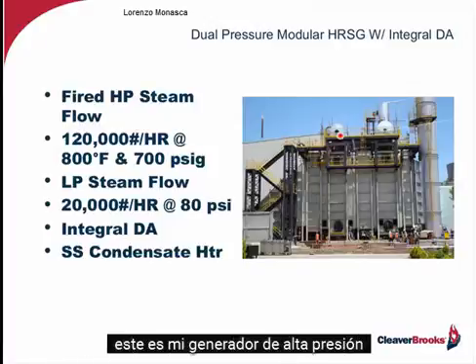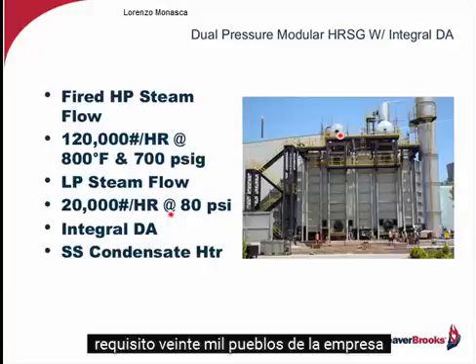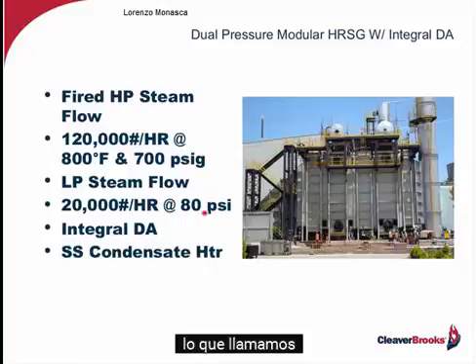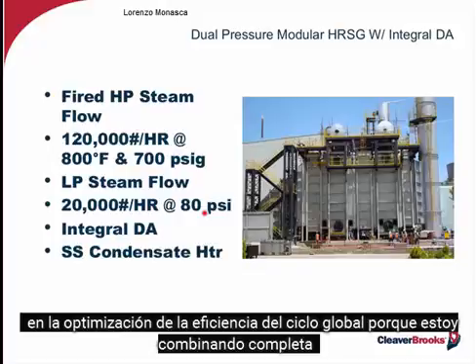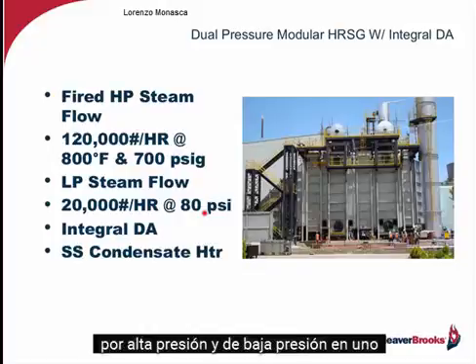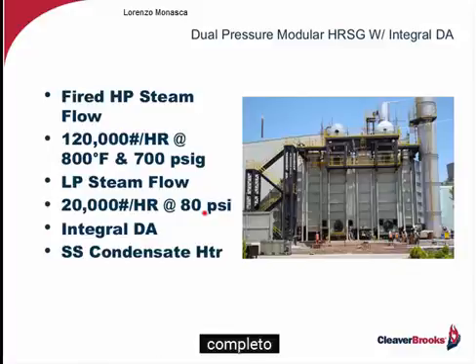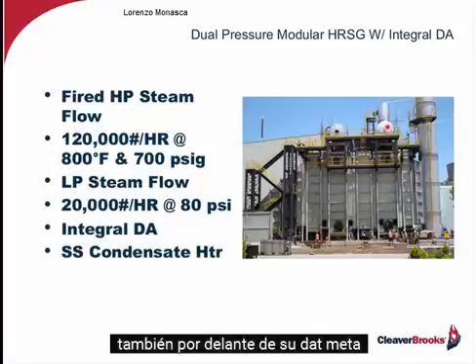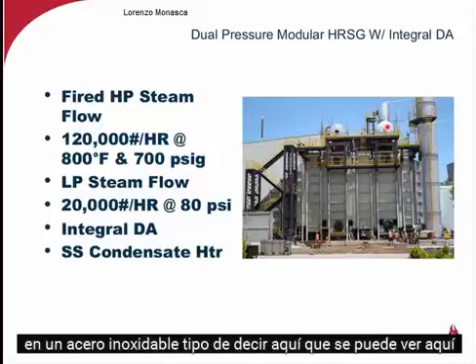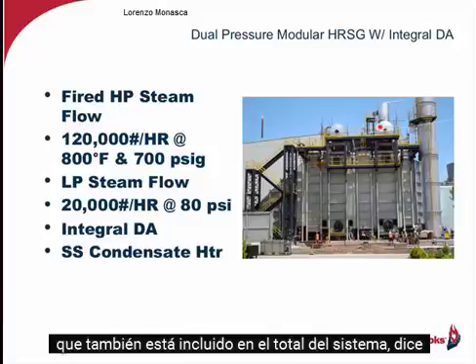This is my high pressure generator. I also have a low pressure requirement, 20,000 pounds at 80 pounds. What we call that is optimizing the overall cycle efficiency, because I'm combining both my high pressure and low pressure into one complete package. It also has an integral DA, deaerator, and a stainless steel condensate heater that you can't see here, but that's also included in the overall system.